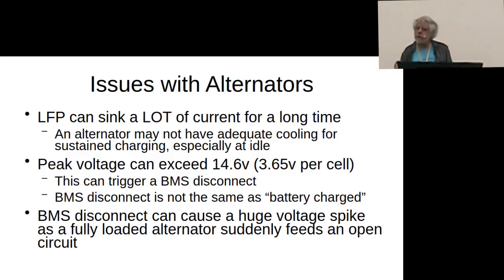Lithium batteries are way bigger in capacity than lead batteries, so the alternator isn't going to be happy with that, especially at idle when it's not spinning very fast. And then there's that disconnect we talked about, which can fry the diodes. So you've got to be careful. You can use an alternator, but you need one designed for that environment. Usually what you do is charge a lead battery and then do a DC to DC converter from the lead to the lithium, or get a specialized charger designed for that.